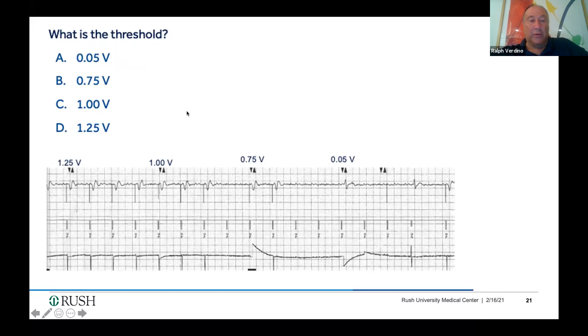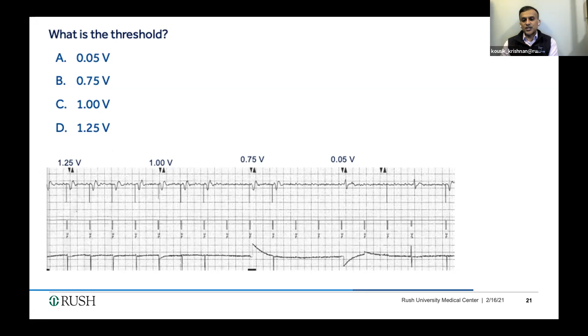0.75. So here at 1 volt, we do have capture for 3 beats, but here there's a V pace, but we don't see a QRS after it. So we don't have consistent capture at 1 volt. But at 1.25, there are 4 pulses given, and all 4 have resulted in capture. Whereas at 1 volt, 3 out of the 4 pulses have resulted in capture. So here, the output that results in consistent capture is 1.25.